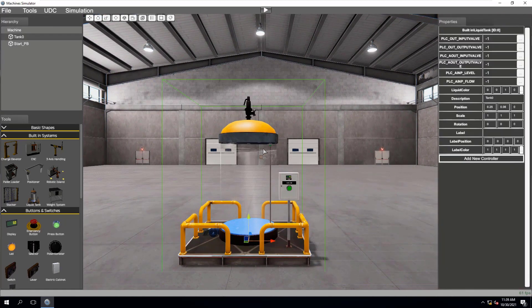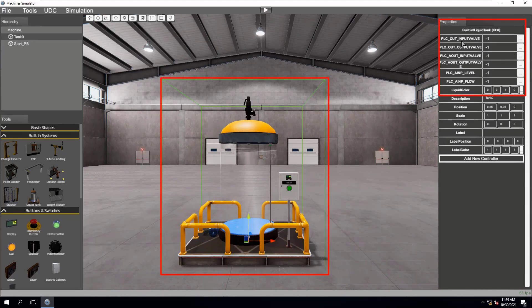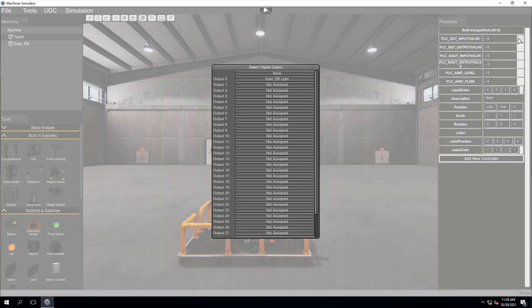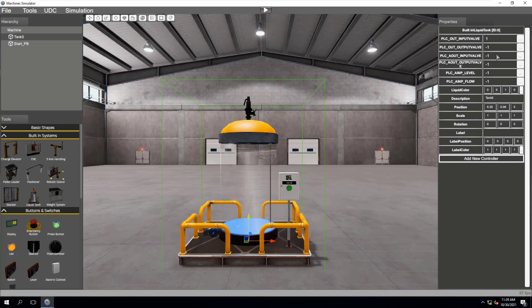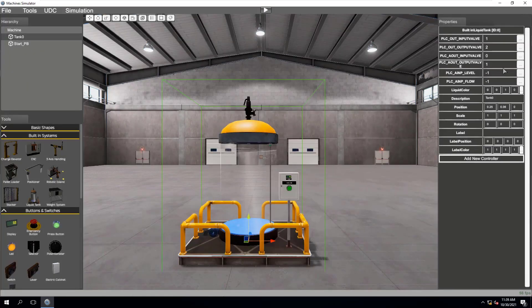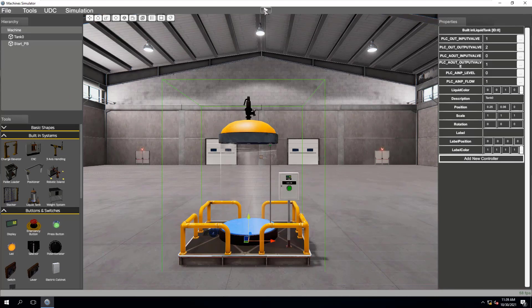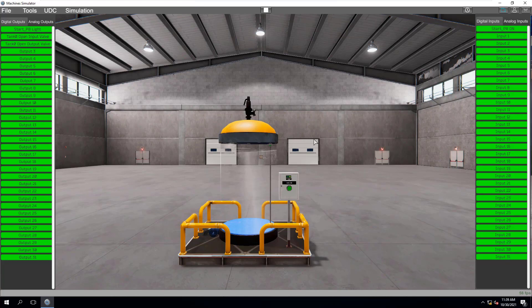Let's go up a little bit so we can see this. We're going to assign the valves for the pre-built machines — you can assign the valves right here. This is the PLC input valve, and this is the output valve. We'll assign output one, then the next output in ascending order, and assign all our inputs and outputs. They also have analog values, so we'll add the analog for the tank level. I'll show you how to add all this — now we have our IO map, and we're going to go to Simulation to verify everything works.